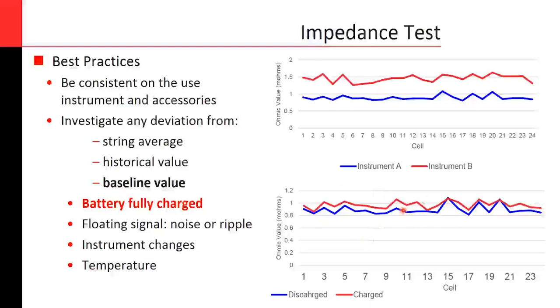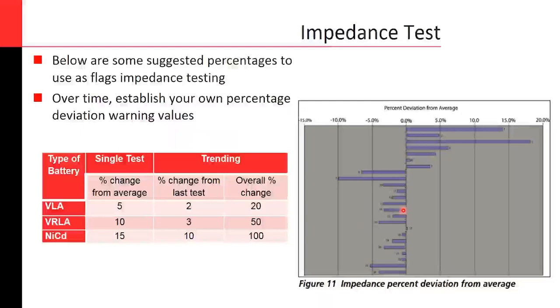And the charge level of the battery is also important. Here you can see a battery fully charged in red for each cell, and the same battery slightly discharged. It was left without any charging signal for like 1 day or 2 days. It was naturally discharging without any load, and you can start seeing some changes in the impedance values there. So these things will definitely affect your results, so that's why we put them as best practices to always keep them in mind.